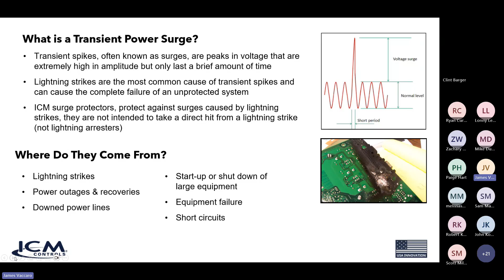If you look at the picture in the lower right-hand side, that's pretty common in a lot of parts of the country. ICM surge protectors protect against surges caused by lightning strikes. They are not intended, and this is an important piece, to take a direct hit from lightning. They merely handle the surges that result from them. They are not lightning arresters. You can also get surges from power outages and recoveries, down power lines, startup or shutdown of large equipment, failure, or short circuits.